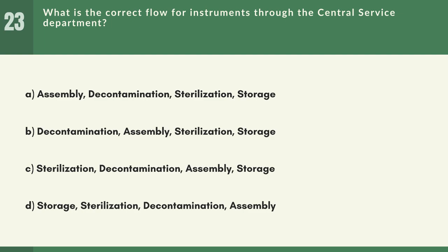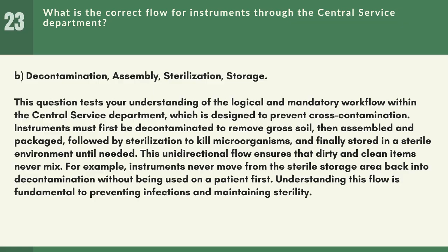Answer: B. Decontamination, assembly, sterilization, storage. This question tests your understanding of the logical and mandatory workflow within the Central Service Department, which is designed to prevent cross-contamination. Instruments must first be decontaminated to remove gross soil, then assembled and packaged, followed by sterilization to kill microorganisms, and finally stored in a sterile environment until needed. This unidirectional flow ensures that dirty and clean items never mix. For example, instruments never move from the sterile storage area back into decontamination without being used on a patient first. Understanding this flow is fundamental to preventing infections and maintaining sterility.